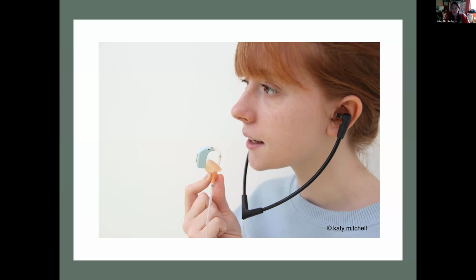Okay, so we're going to take it hearing device by hearing device. We're going to start with hearing aids. And like I said, I'm going to focus a lot on a listening check. So first we have to know how to do a listening check. For a hearing aid, we should all have that listening tube of some kind. To perform a listening check, you just put the bottom end onto the ear mold piece, and you want to make sure that it's covered completely. Otherwise, you're going to hear a lot of whistling. So make sure it's in there deep enough and has a good seal.